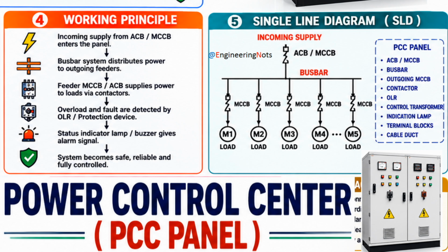At the same time, the current transformers measure the current flowing through the system. The measured values are sent to the protection relays and the digital power meter. This allows engineers to monitor the electrical system continuously without interrupting the power supply. Finally, the electrical power leaves the PCC through the outgoing feeders. Each feeder supplies another electrical panel, a motor control center, or a large industrial load.